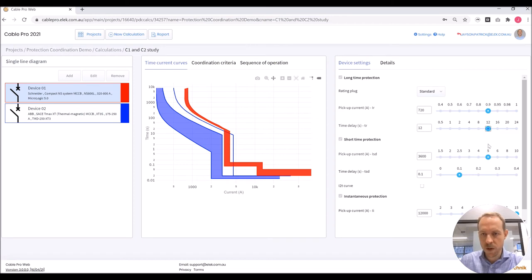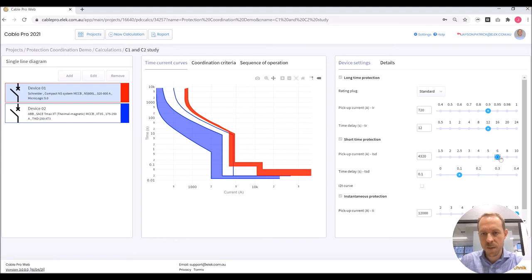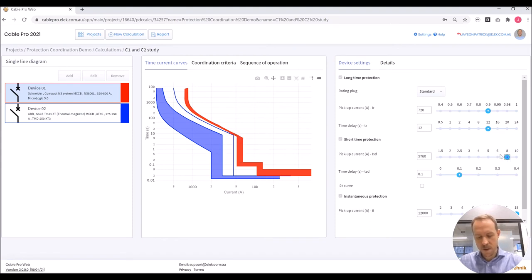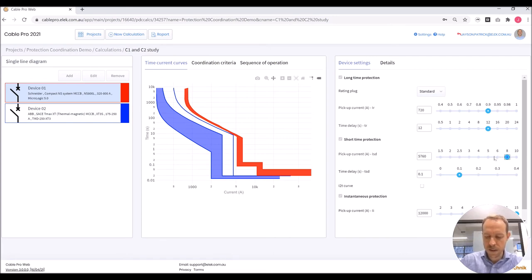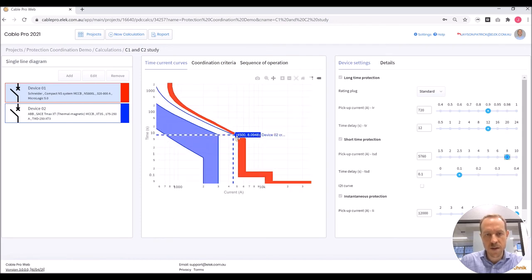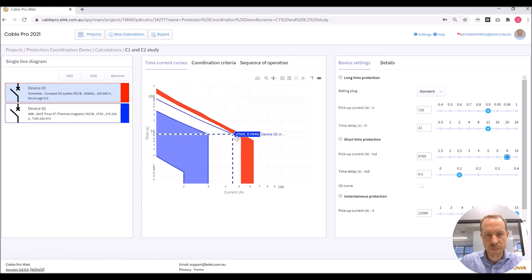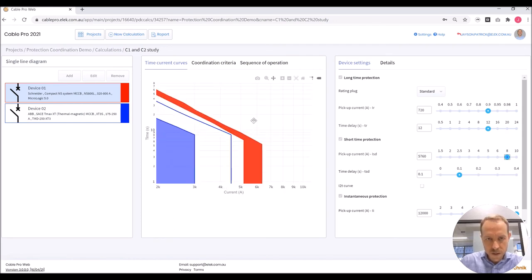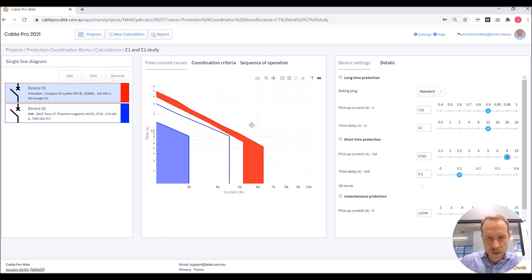Finally, I'm going to adjust the short time protection and the pickup current. We can see that these changes have helped us to achieve discrimination. And we can check by zooming in on the plots.